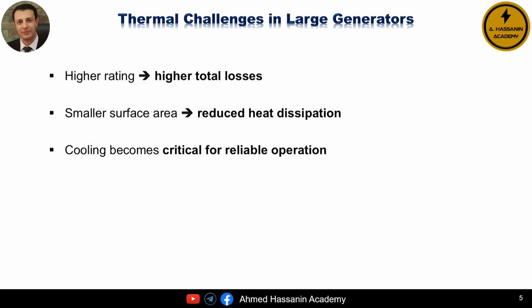Alright, now let's look at the thermal side of the problem, because this is where things start to get serious in large generators. As the generator rating increases, the machine produces more total losses, mainly electrical and magnetic losses, and all of that loss energy turns into heat. At the same time, modern generator designs aim to be more compact, so the available surface area for heat to escape doesn't increase at the same rate.